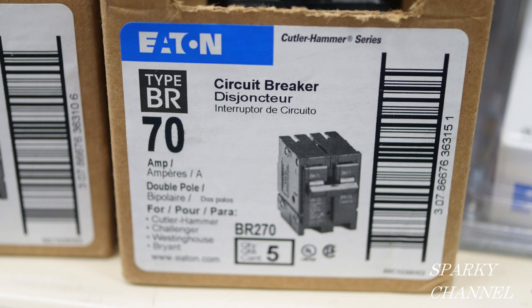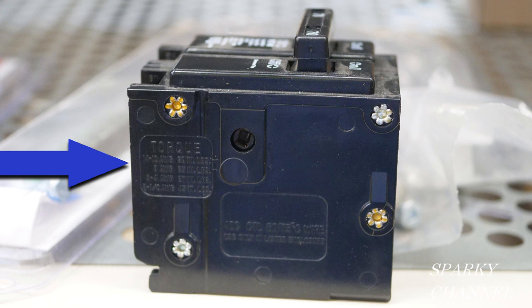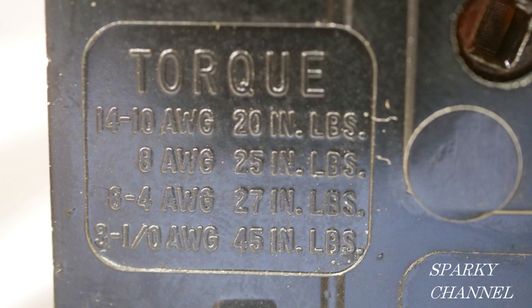Now I'll show you some examples of where to find those torque values on specific breakers. This is an Eaton 70-amp breaker and the torque values can be found right where the blue arrow is pointing. Notice that the torque values will vary depending on what size wire you're putting under that breaker terminal. For instance, for 14 to 10 AWG it's 20 inch pounds, for 8 AWG it's 25 inch pounds, for 6 to 4 AWG it's 27 inch pounds, and for 3 to 1-aught AWG it's 45 inch pounds.